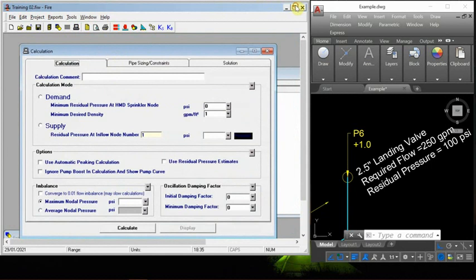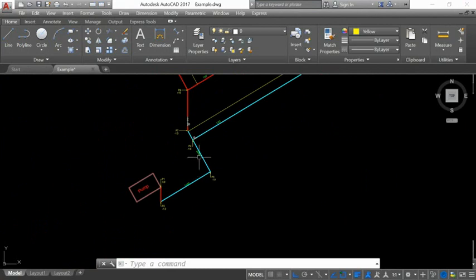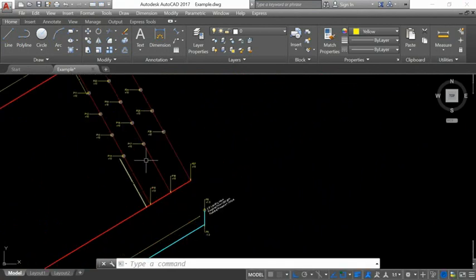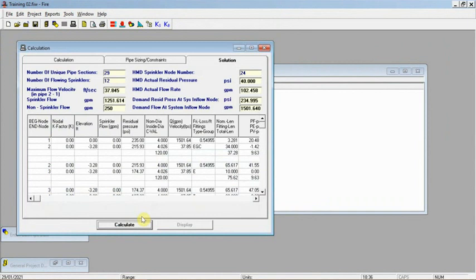Now we are at the calculation step. I am calculating at demand with a residual pressure of 40 psi. The assumed pipe sizes are: underground and main loop at 4 inch, branch lines at 2 inch. After running the calculation, the result shows we need a pump delivering 1500 gpm at a pressure of 234 psi.